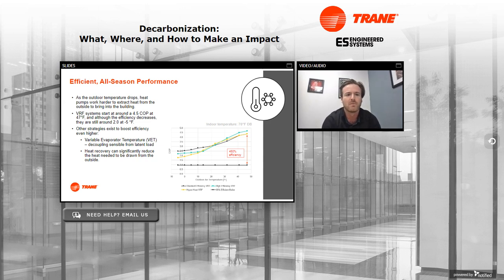There are a couple other strategies that can be used to boost your efficiency with VRF systems. One of them is called variable evaporator temperature. What this does is you can use a DOAS system to decouple your sensible cooling load from your latent cooling load. Granted, this is more of a cooling side application, but you can boost your VRF efficiency by up to 30% by raising your evaporator temperature. That's a whole other discussion we could talk about a different day, but something to be aware of. Additionally, you have heat recovery, which we already hammered on a little bit. You are reducing the amount of heat you have to draw from the outside, which really can improve your efficiency on the system overall.